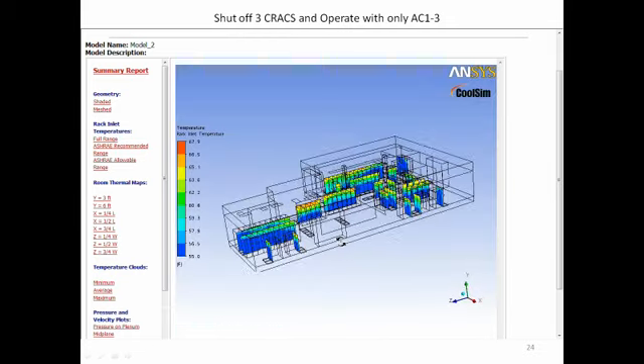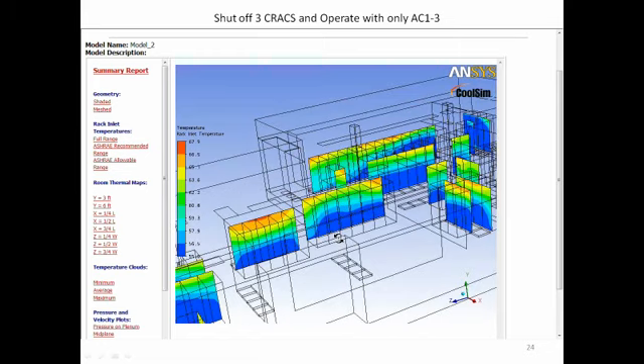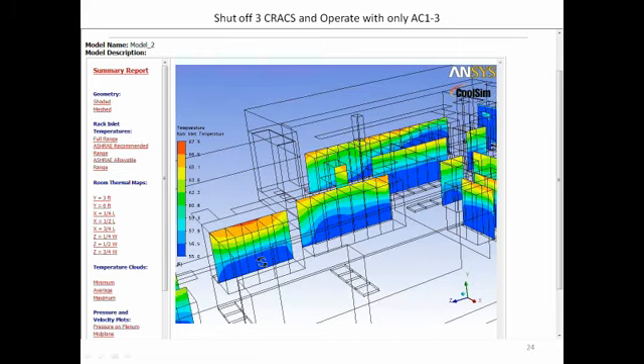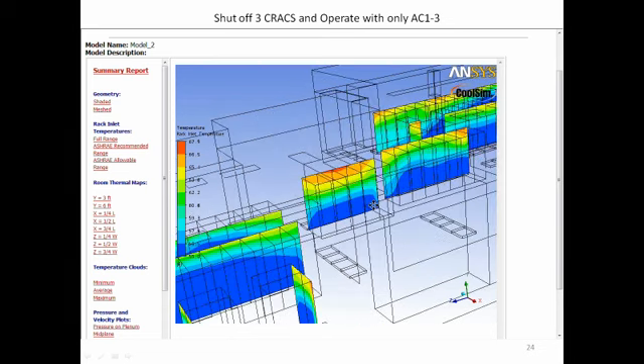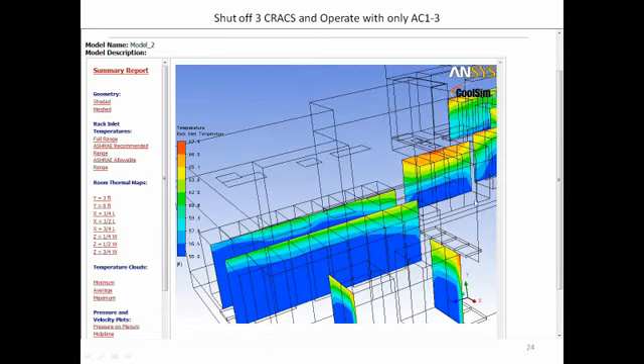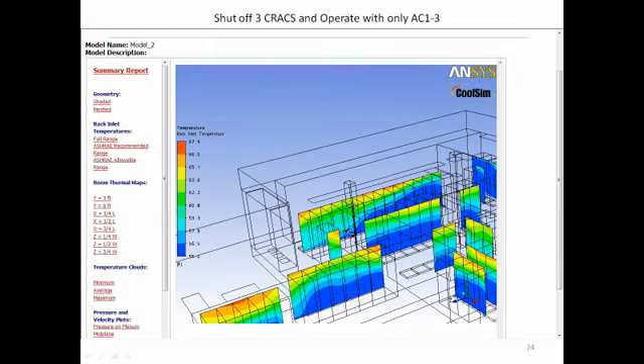Look at the full range, you're going to see quite a bit of variation. Because we're not managing the airflow, we've got quite a contour over here, quite a bit of temperature over here, and down here as well. It's also interesting to note that in this region, high velocity air is coming right by here and causing it to be cold at this end, but hot at this end because we're so close to that high velocity air. Close to the CRAC. Too close to the CRAC.